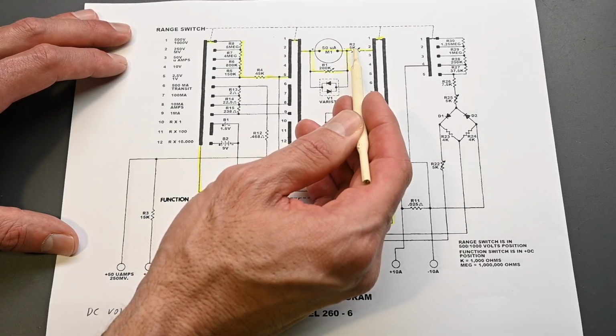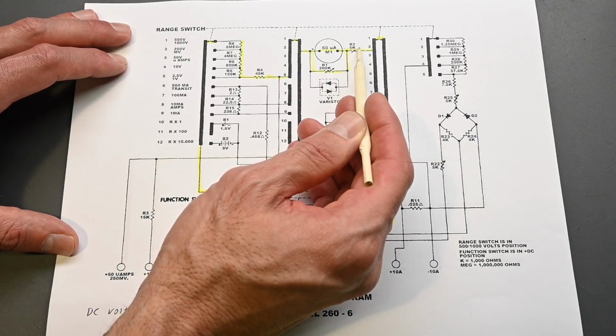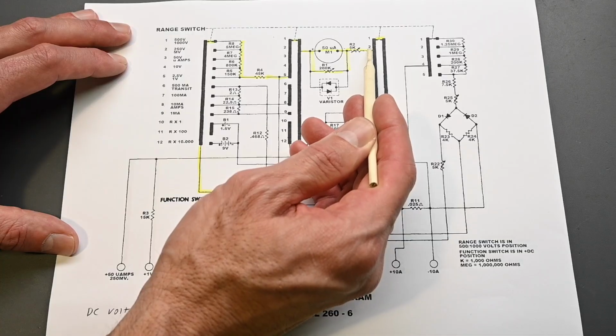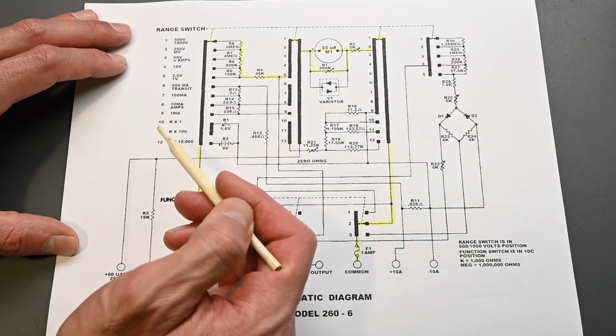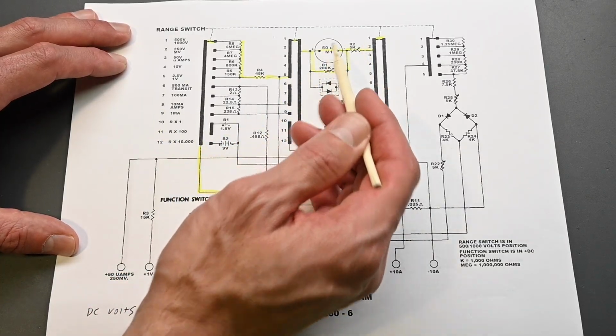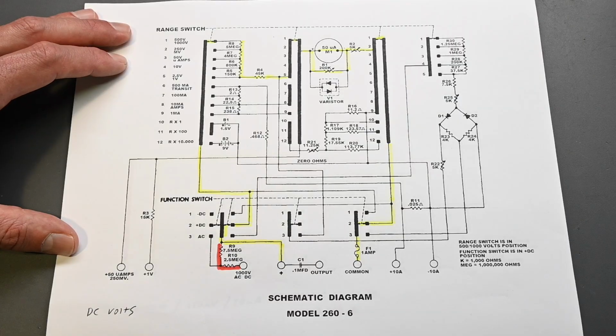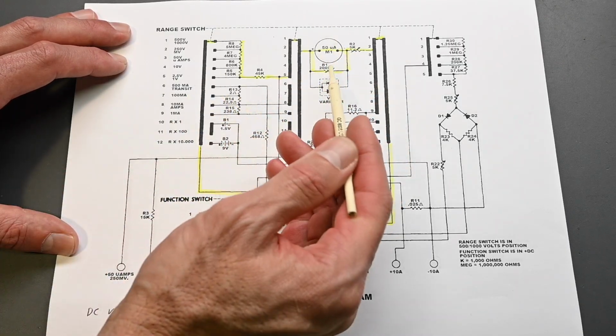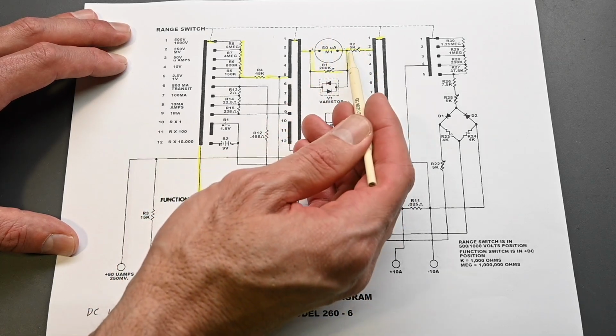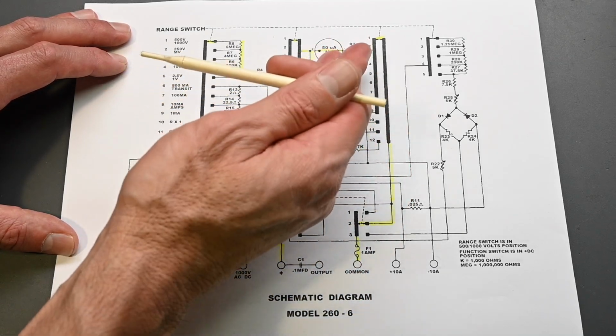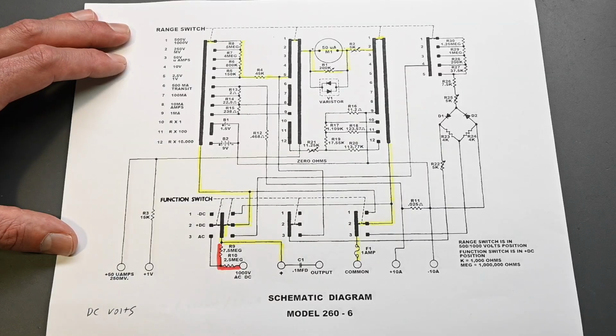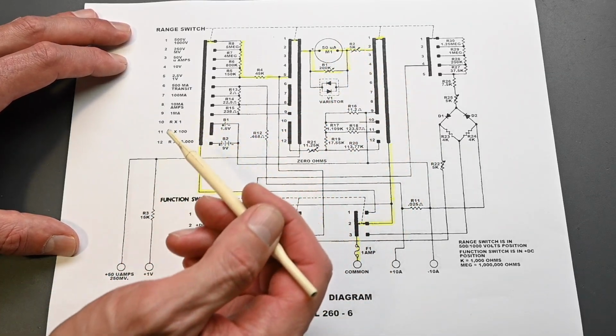And then this 5,000 ohm potentiometer is set so that the total resistance from this point to this point is 5,000 ohms. So 5,000 ohms across here is 50 microamps and 250 millivolts full scale deflection. And this calibration is very important, because if this is off, then it's incorrect for any of the measurements that the meter can make.